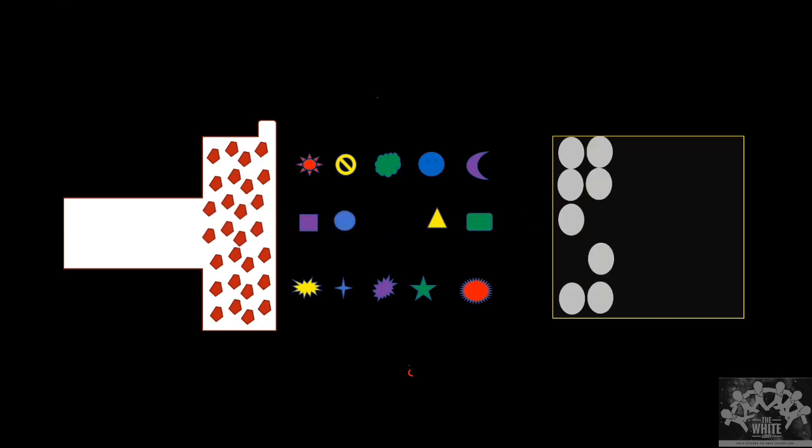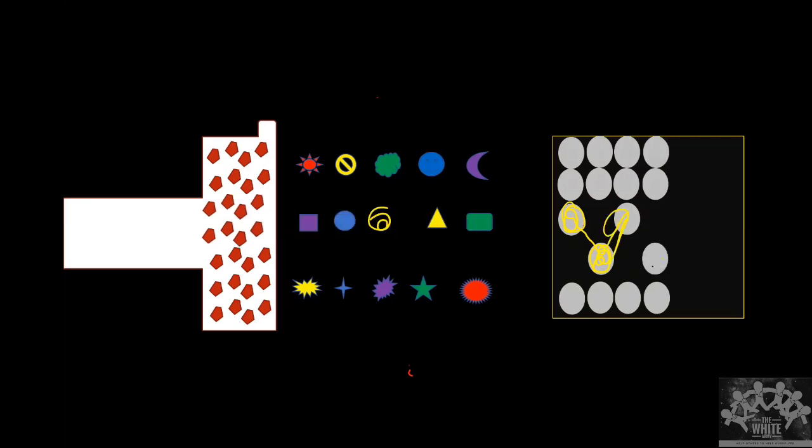Now the structure was here, which moved here. Again the structure might move back. When I image this, I get an image like this. Again the structure moves in one more direction, again it comes here, and in the next image it is here. So we get a wave showing whichever structure is moving. Yes, M mode is serial B mode.